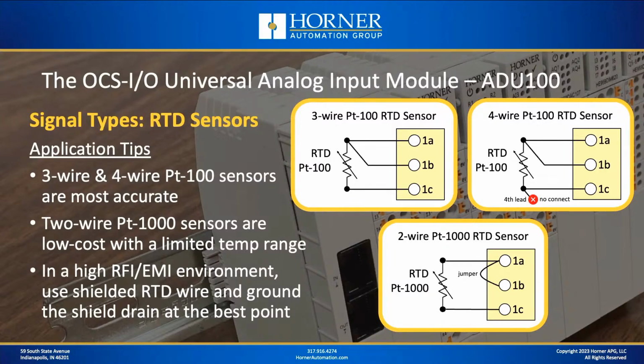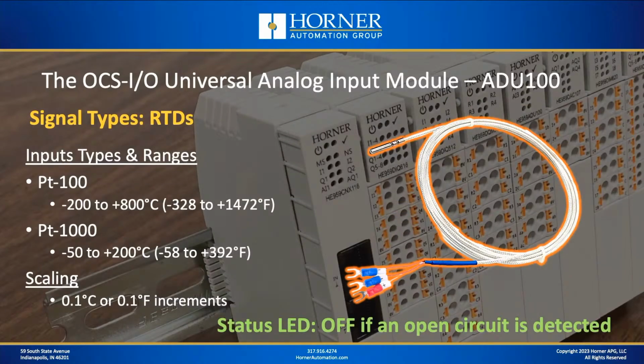Now, if you've got an application with a fair amount of noise, I would recommend that you opt for shielded RTD lead wire and properly ground the shield, of course, to eliminate EMI and RFI in your application as much as possible. So again, if you think there's electrical noise around, you're doing some heating or something at some higher voltages, I would encourage you to use shielded wiring as well with RTDs. Now, in terms of the temperature ranges that are supported for PT100s and PT1000s, you can see there on the screen that the PT1000s are much more limited in terms of their temperature range. Now, in terms of the format in which the temperatures come back, you can select in configuration between degrees Celsius or degrees Fahrenheit, and the values come back already in 10th degree increments.